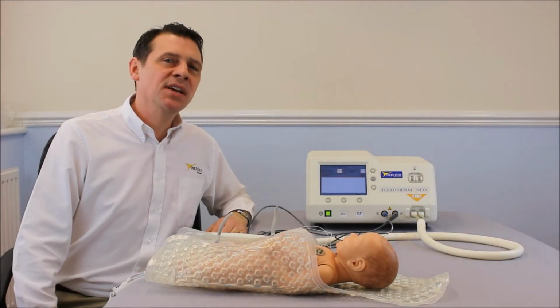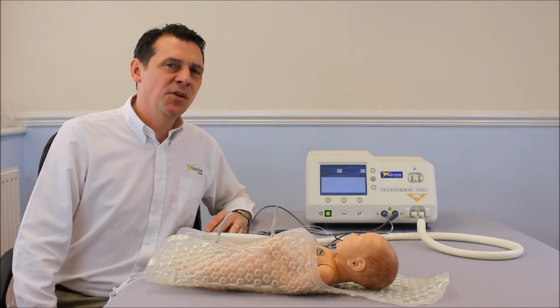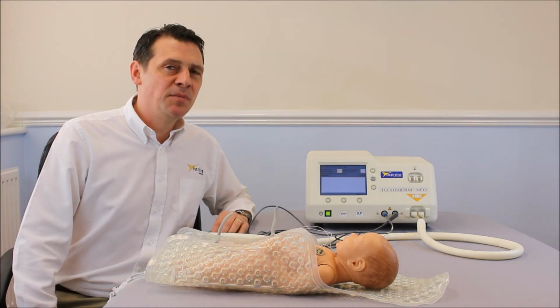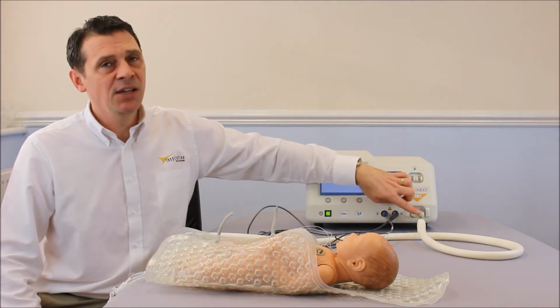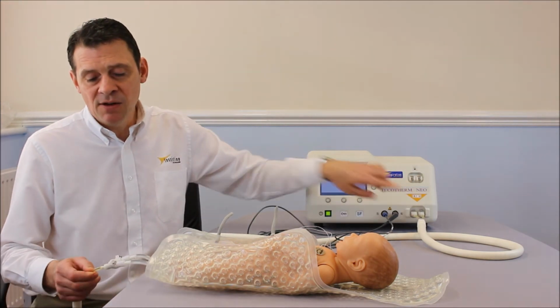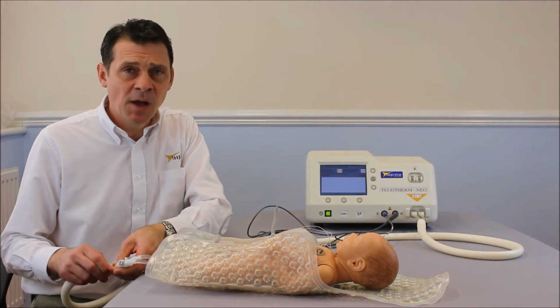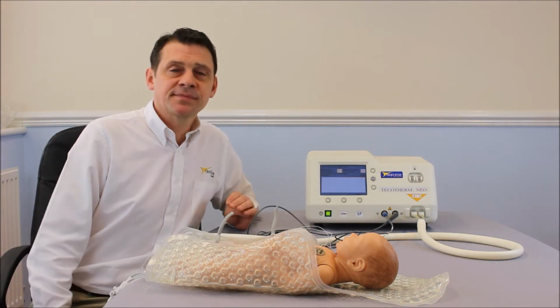There are a number of alarms that can occur during operation of the Tecotherm Neo. One of them is the no-flow alarm. This will occur if you have a kink in your tubes here. Make sure that they are all straight, and any kinks that you have, just unbend them or untwist them.